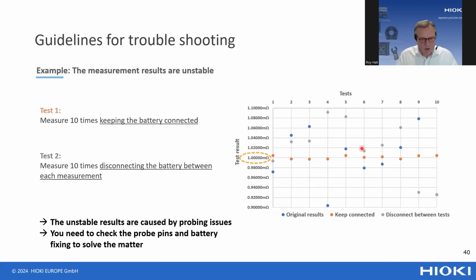And when you know that making contact to your battery is the issue, you can focus on looking at what the problem might be. It could be that your probe pins need to be replaced because they have worn, but it can also be that they are not fixed in a proper way and that there is a little tolerance when you are probing with your battery. Or it could even be that the battery is not firmly fixed before you're going to do the measurements. And if the battery moves slightly, that will also give you a poor reproducibility of the measurement. But with this test, you narrow down the possibilities of problems. And that's basically the message that we want to send out.